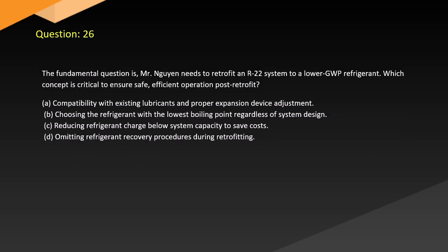Question 26. The fundamental question is: Ewan needs to retrofit an R22 system to a newer refrigerant. Which concept is critical to ensure safe, efficient operation post-retrofit? A. Compatibility with existing lubricants and proper expansion device adjustment. B. Choosing the refrigerant with the lowest boiling point regardless of system design. C. Reducing refrigerant charge below system capacity to save costs. D. Omitting refrigerant recovery procedures during retrofitting.